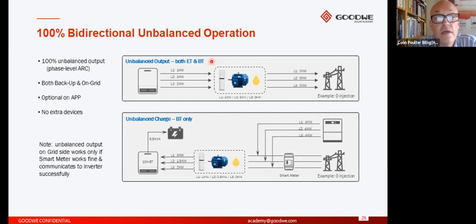Now, because we are able to configure the inverter to support unbalanced loads, if this inverter was generating its maximum of 3.3 kilowatts on each phase, however, as I said, we're not allowed to export anything to the grid, then because we have unbalanced load capability, each phase output of the inverter is able to supply the needs of the loads on each phase. Phase 1 needs a load support of 1 kilowatt, so phase 1 of the inverter will produce 1 kilowatt. Phase 2 is 3 kilowatts, and that's what phase 2 of the inverter will produce, and so on. Load 3, 2 kilowatt requirement, and that's what the inverter is going to produce.